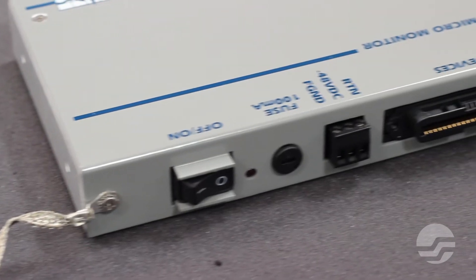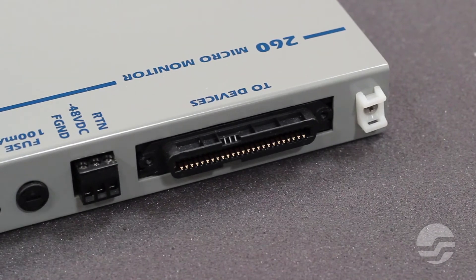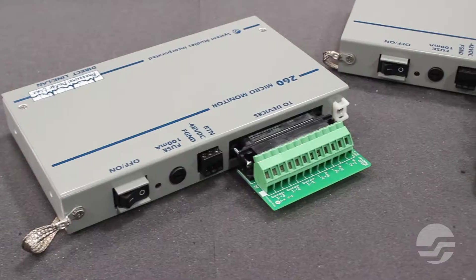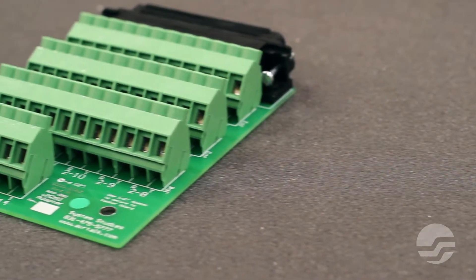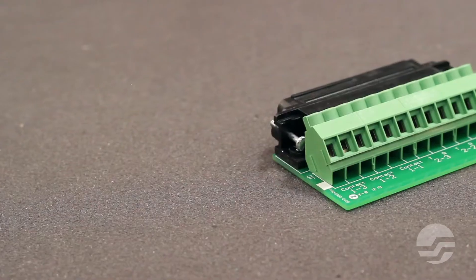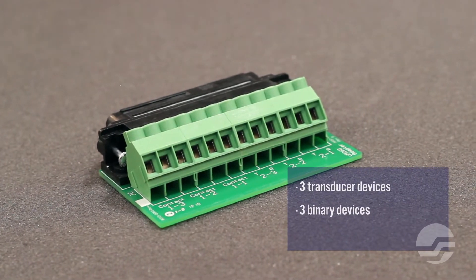To accommodate device pairs from the field, the monitor is equipped with a single 25-pair female Amphenol connector. As an alternative to terminating devices at a standard connector block, System Studies offers two termination adapters to allow direct plug-in connectivity. Our 21-pair adapter accommodates the full monitoring capacity of the UM260 Micromonitor. Our 6-pair adapter is designed for a maximum of three transducer devices and three binary devices — ideal for very small offices where a Dial-A-Ducer is being replaced. For this demonstration, we will be using our 6-pair termination adapter.